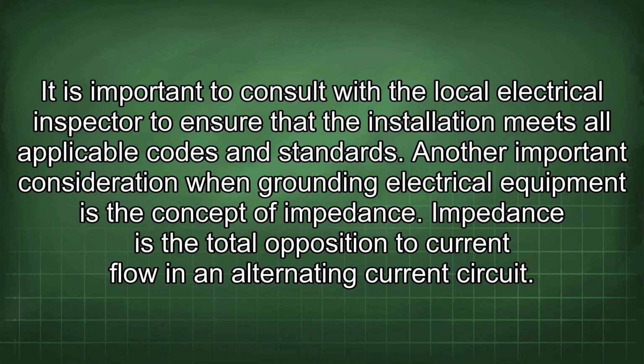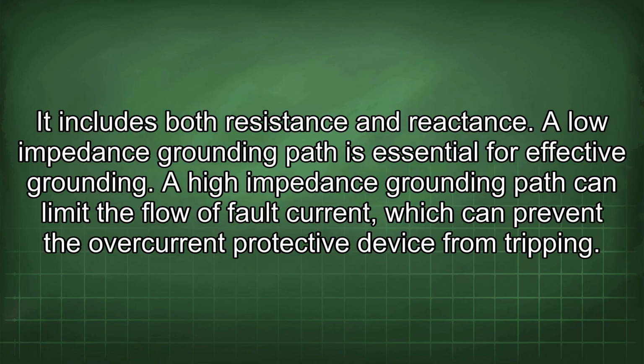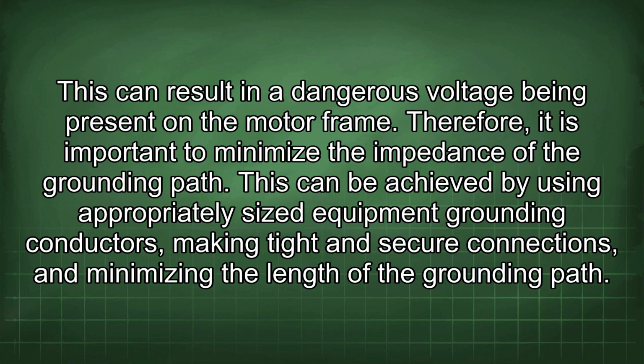Impedance is the total opposition to current flow in an alternating current circuit. It includes both resistance and reactance. A low impedance grounding path is essential for effective grounding. A high impedance grounding path can limit the flow of fault current, which can prevent the overcurrent protective device from tripping. This can result in a dangerous voltage being present on the motor frame. Therefore, it is important to minimize the impedance of the grounding path.